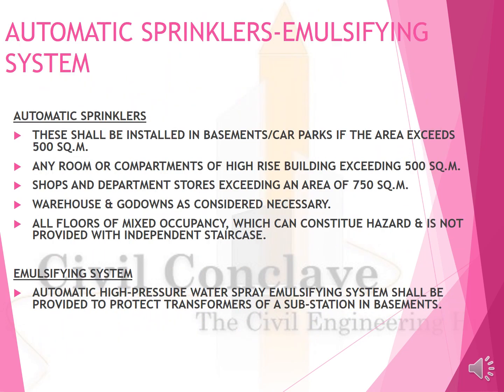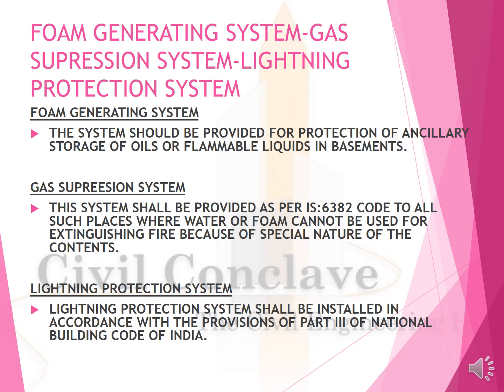Automatic sprinklers. These shall be installed in basements and car parks having an area of more than 500 square meters, any rooms or compartments of a high-rise building exceeding 500 square meters, shops and stores exceeding 750 square meters, and warehouses and godowns. Emulsifying system. An automatic high pressure water spray emulsifying system shall be provided to protect the transformer of a substation in a basement.